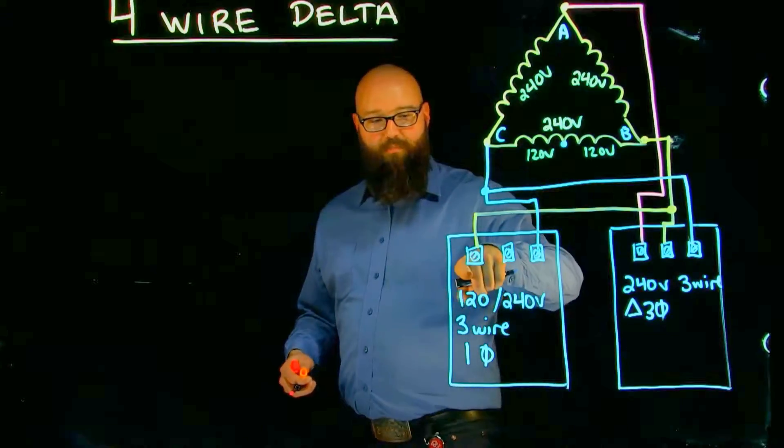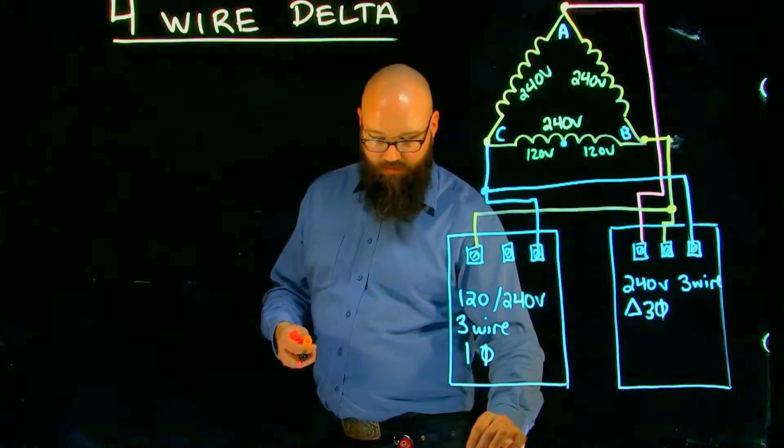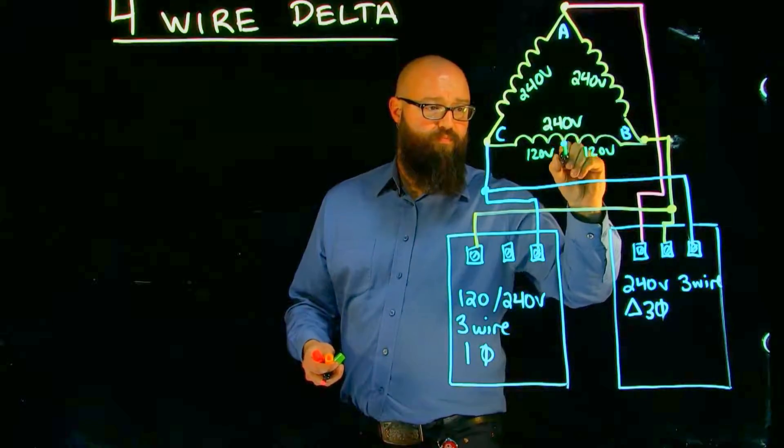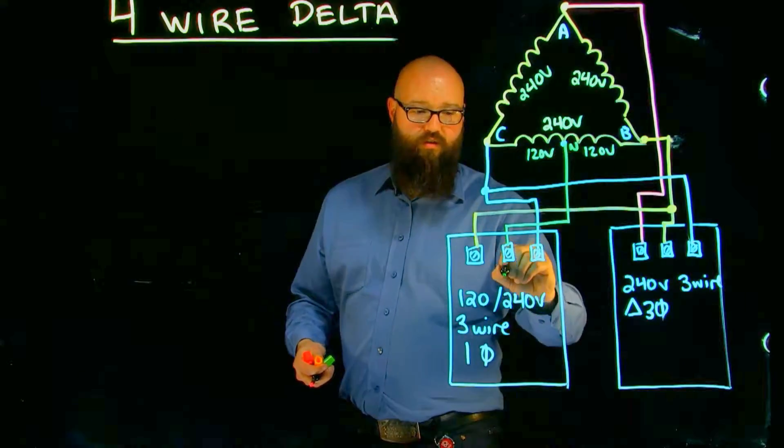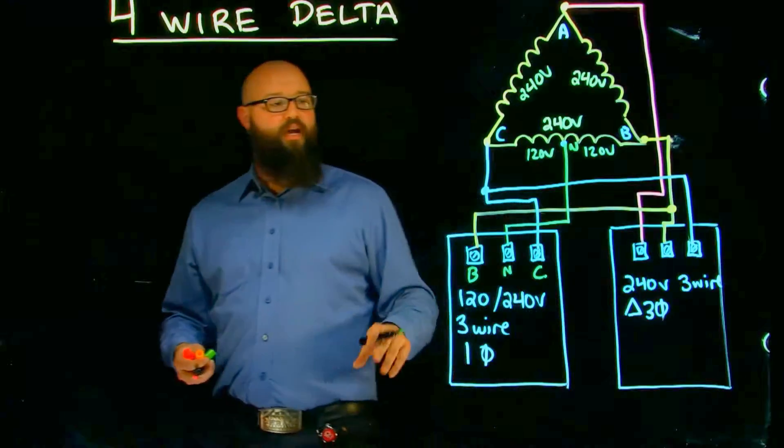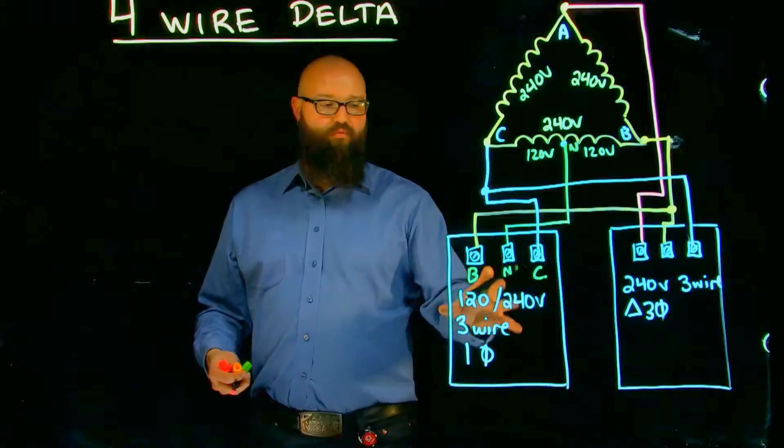Now we have our B phase, our C, sorry our B line and our C line, and right in the middle we're going to bring down this common or neutral point. Right down into there. There's our neutral, there's our B, there's our C, and we end up with a 120/240 volt single-phase three-wire system.